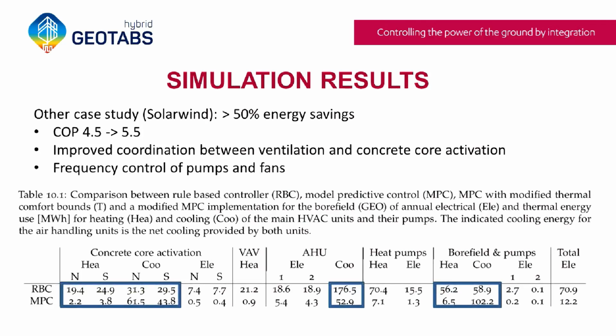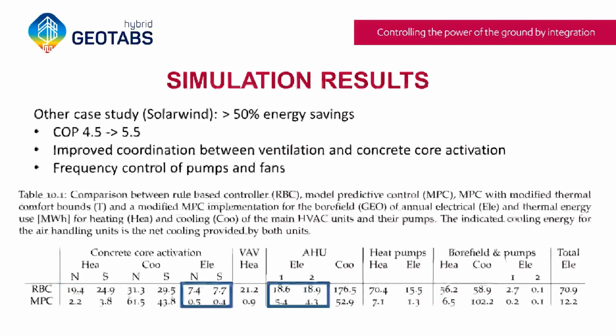What sometimes happens is that you cool and ventilate at the same time using different systems, and MPC is very well able to avoid that, which drives the overall cooling and heating load down. For instance, here you see a reduction of the cooling load from the air handling units by a lot, but that of course shifts towards the bore field, which is then again a problem. But that's another part of the solution that we found. And the third part is the frequency control of pumps and fans.